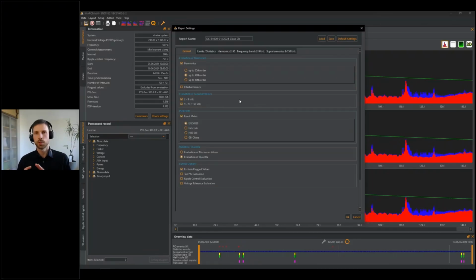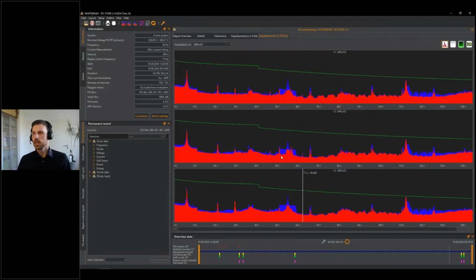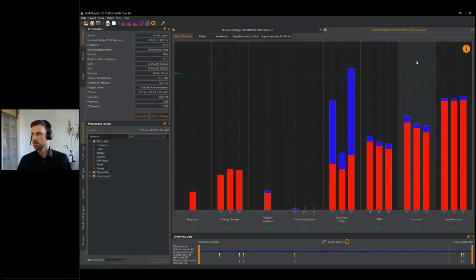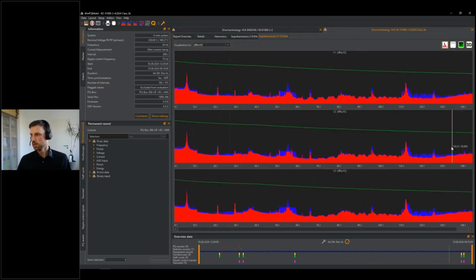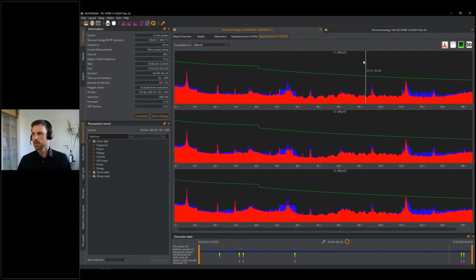I will open, and PQ-Mobil automatically adjusts the settings. I confirm with OK, and now I can do the norm evaluation again. So I open this again, new window, and here at the very top I see in the title of the tab, this is IEC 61000-2-4, and previously it was the default setting. So in here, I can always click on flicker, supraharmonics, and so on, and check the values. As you see, these are slightly different. The measurement data is the same, but the limit values change a little bit. You see the green line, it's different.